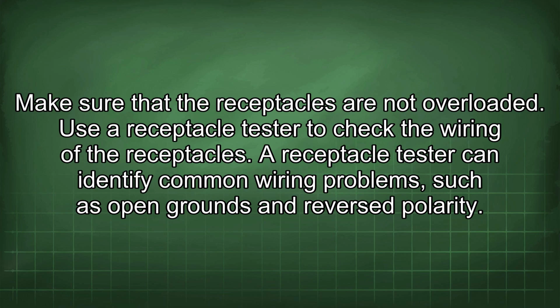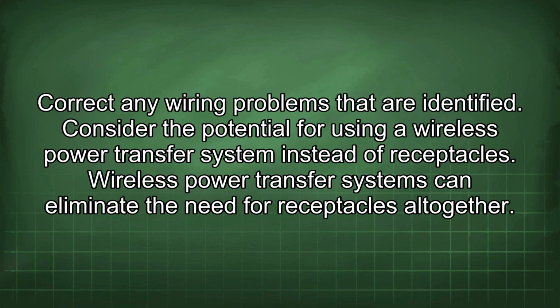Use a receptacle tester to check the wiring of the receptacles. A receptacle tester can identify common wiring problems such as open grounds and reversed polarity. Correct any wiring problems that are identified.